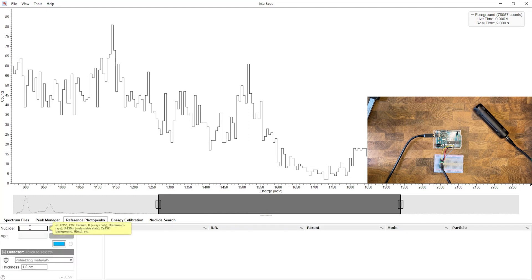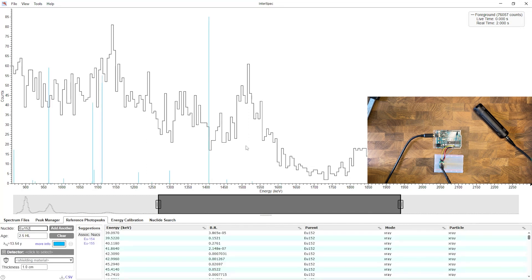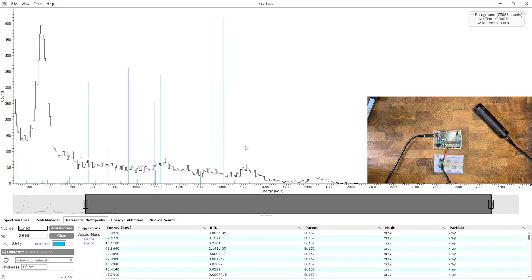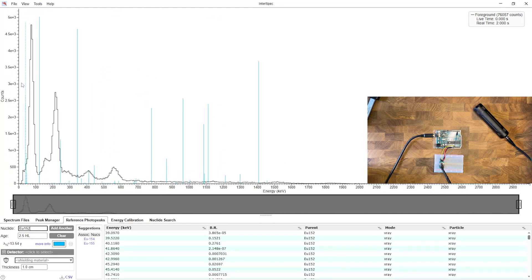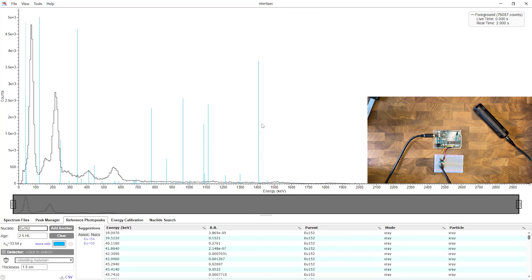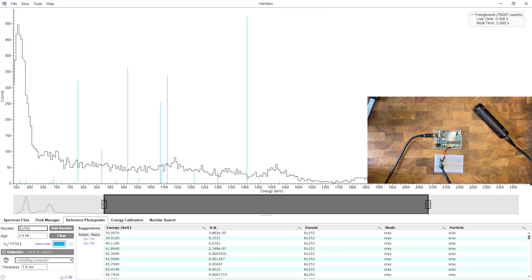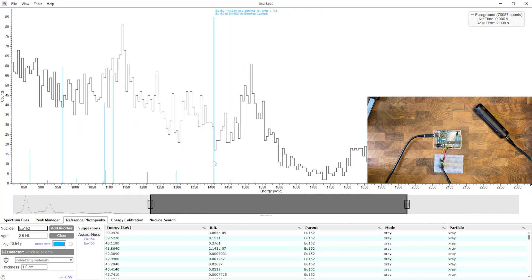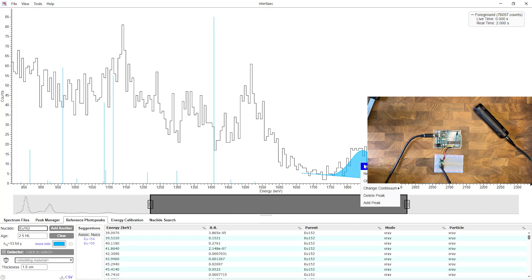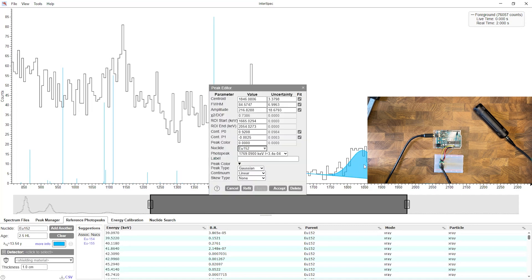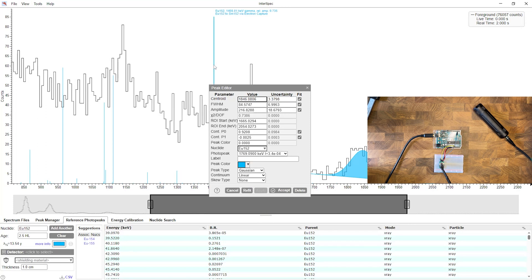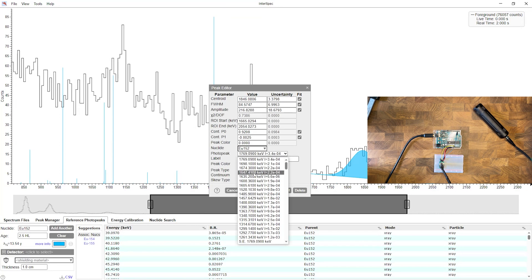So what I'd recommend doing for calibration is if you know what your isotope is, head over to reference photopeaks and we can search for EU-152 for europium-152. You could do radium-226. So if we zoom out here, we can see a whole bunch of lines. These lines are telling us where our peaks should be. It's not calibrated right now, so they're clearly not there. So this really big peak out here needs to actually be over here. And so we can do is double click on it and it highlights it. And then we can right click and go to peak editor and we can see that it is selected at the wrong value. So it should be at 1408 and we can see that right over there. And so I'm going to go through each one and make sure they're in the correct areas.